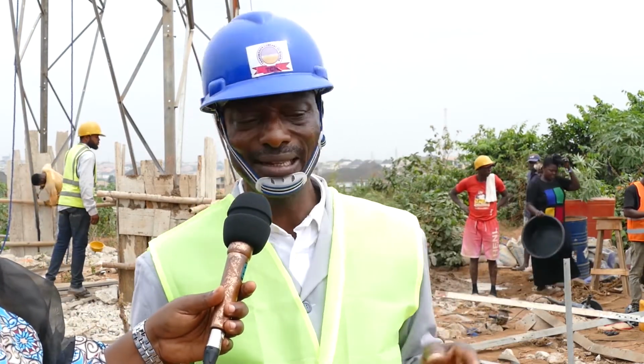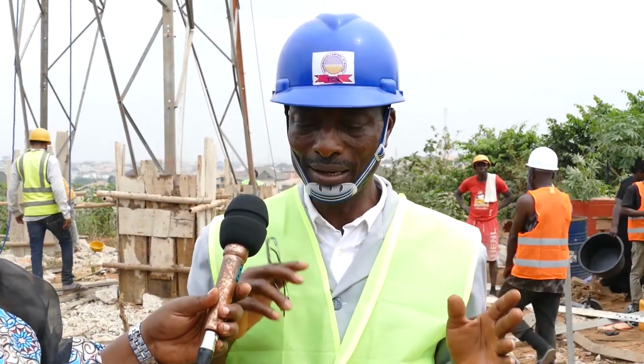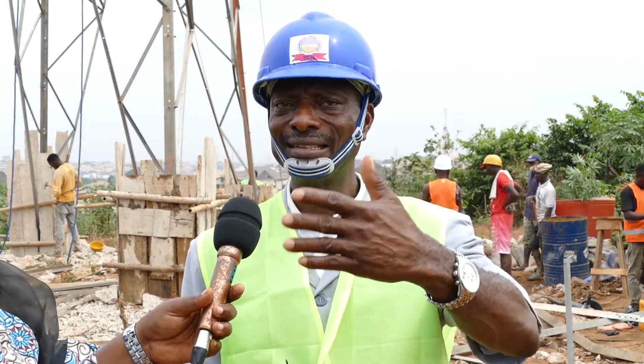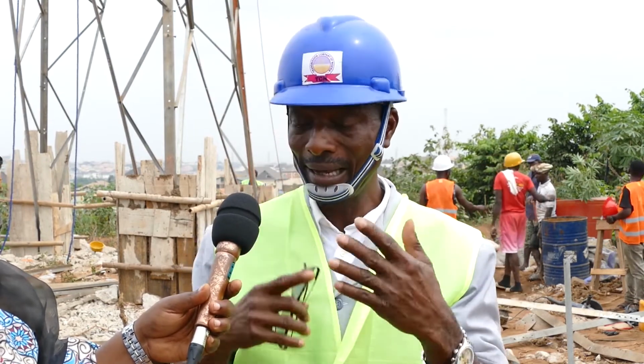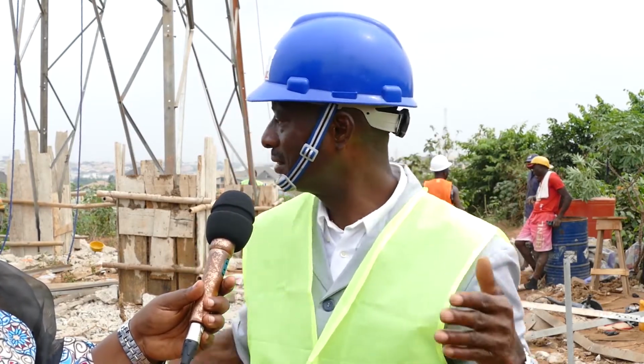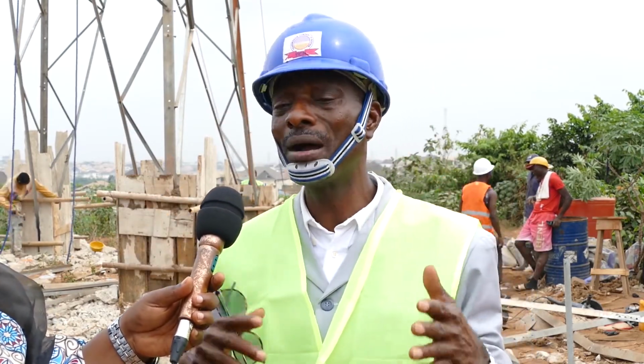The capacity that this line used to carry was 145 megawatts before. Though we have two lines paralleling each other, we are using one leg as a redundant leg, and that is why it looks as if nothing has happened. Right now we are using the other line, but this particular line was carrying 145 megawatts on the day this thing happened.